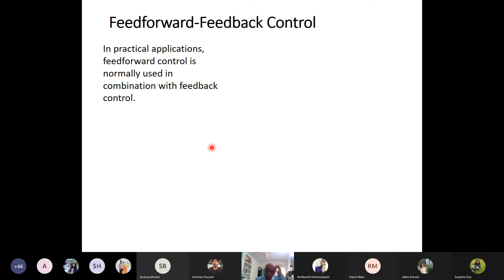In this case, we have the normal feedback control. The feedback controller output, the level controller output, is further augmented by the feed-forward controller output over here. The feed-forward controller takes the measurement of the disturbance over here. If you look at this system, you have got two disturbances. One disturbance is the steam flow. Another disturbance is the feed water temperature. The third disturbances are unmeasured disturbances, which are basically the scaling of the boiler tubes, or the reduction of the heat transfer area.